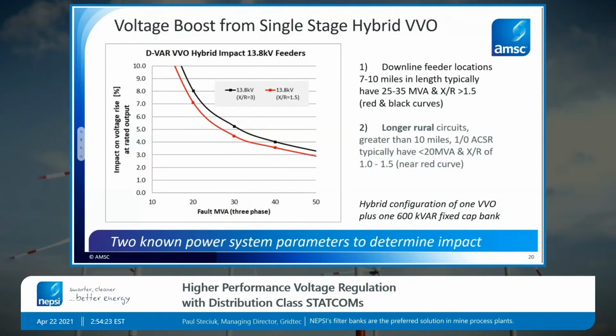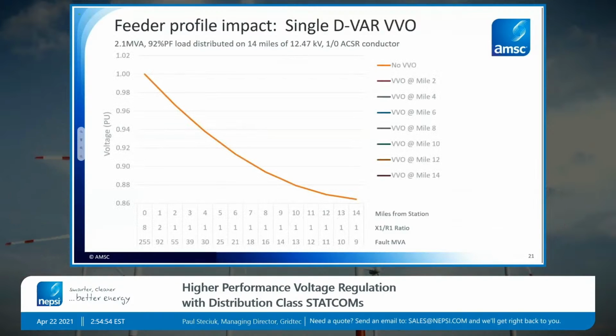So these graphs are basically showing how much impact we have at a single point of installation. So this is specifically where the STATCOM would be installed on the feeder at that one point. It's important to understand how the voltages along the feeder are being impacted by a STATCOM in a voltage regulation application. And that's what's now being shown on the next couple slides here. So what is shown here is a representative feeder that's 14 miles long that has the load spread out along that feeder. And just for clarity purposes, we've actually stripped out all the voltage regulating devices. So what we're seeing here is a profile just due to the load on that feeder.